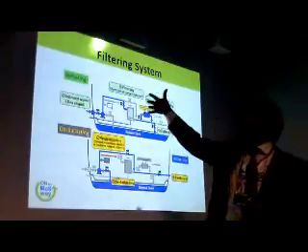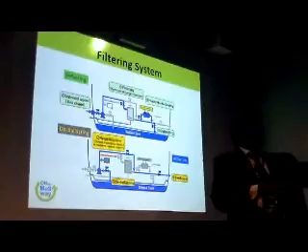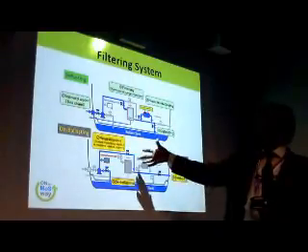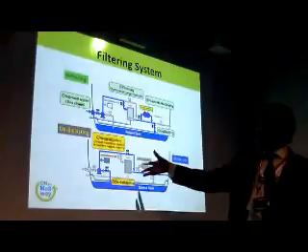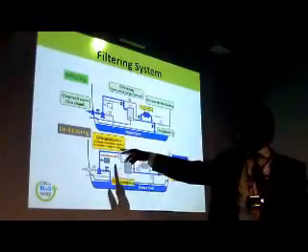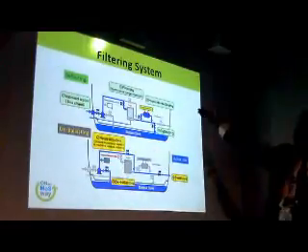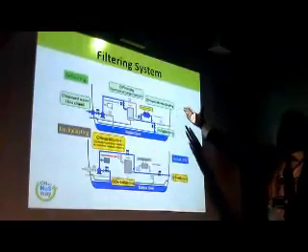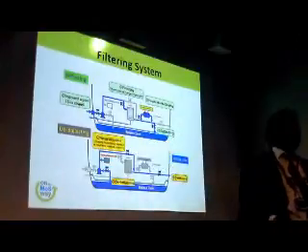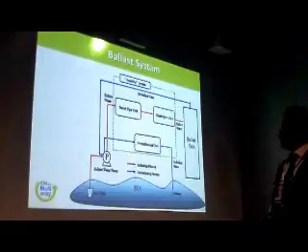When we are ballasting, we are trying to filter out all these invasive species, and when we are going the other way around, we are removing the chlorine from this, because here we are dosing hypochlorite, and here we are neutralizing that, so we are not damaging the environment where we are deballasting our tank.